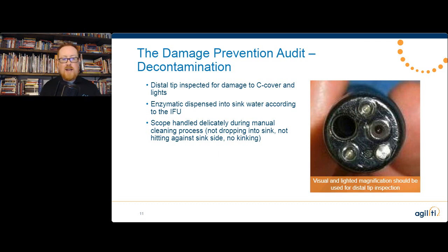And then we also want to see that the scope is being handled delicately through the whole manual cleaning process: not dropping it into the sink, not hitting it against the sink side, no kinking. And I know, especially if you're really experienced at this, you're probably sitting here like, duh. I did not need an in-service to tell me not to drop the scope into the sink. Like, I got it, right? But what we find is that as the pressure is pushing on the technician to hurry up, that technician starts moving very quickly, and as they're moving very quickly, they're thinking about what's the next step, while not being mindful about what's the step I'm on right now.